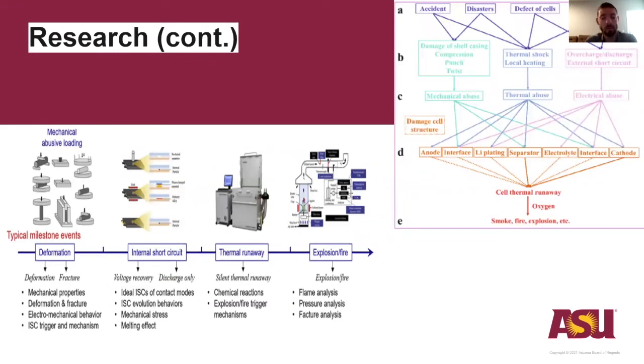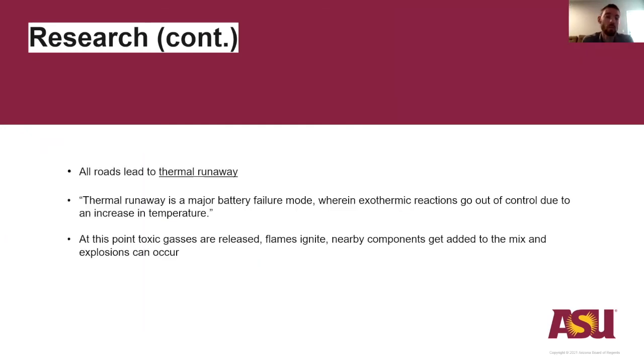I'm not going to spend too much time on this slide. What I want you to take away is that these are typical milestone events, shown here as a flow chart. The common denominator is thermal runaway, seen in both pictures on the left and right. All roads lead to thermal runaway, which is essentially a battery failure mode wherein exothermic reactions go out of control due to increasing temperatures. Basically, all the chemical reactions occurring inside the battery are no longer able to be contained, so they have to go somewhere, and outward is where that goes. At this point, toxic gases, some of which are flammable, are released. Flames can ignite due to the high temperatures and flammable gases present. This can lead to nearby components, whether other parts of the system or other batteries, being affected, and explosions can occur from all of these cascading effects.